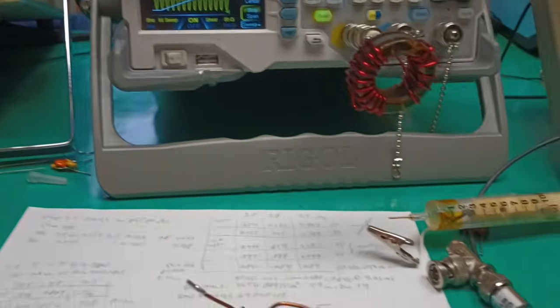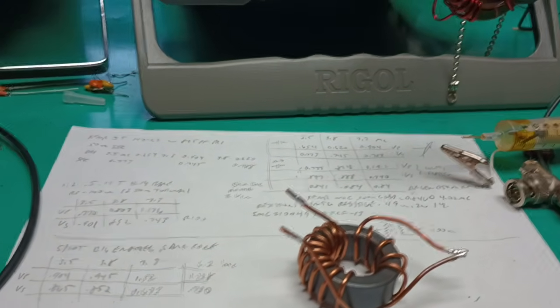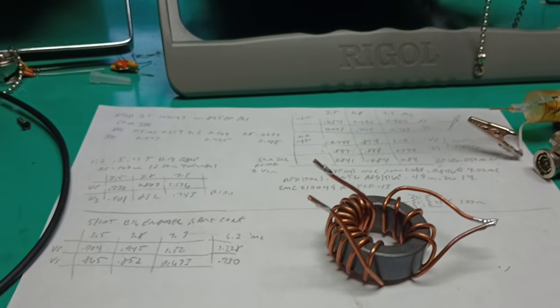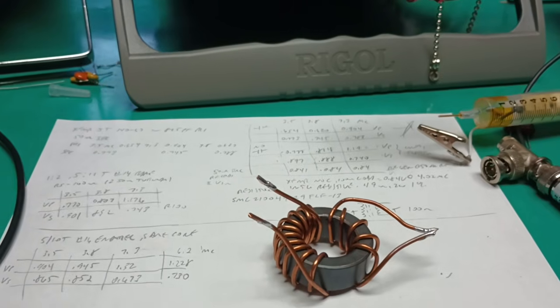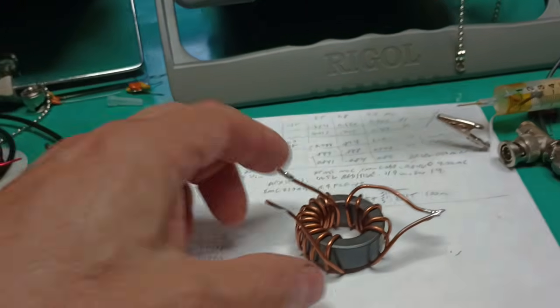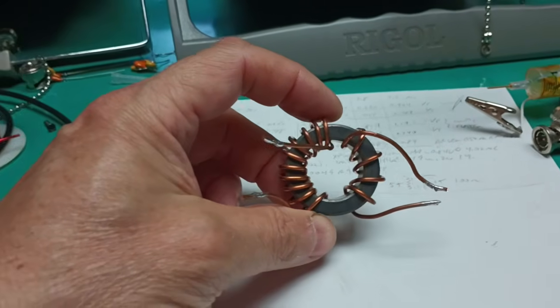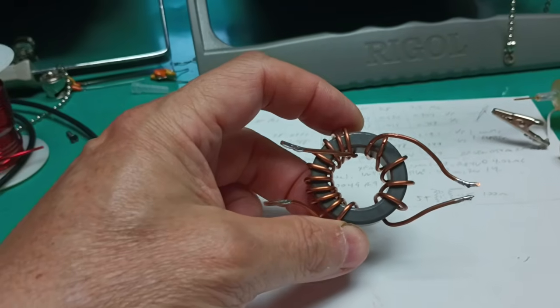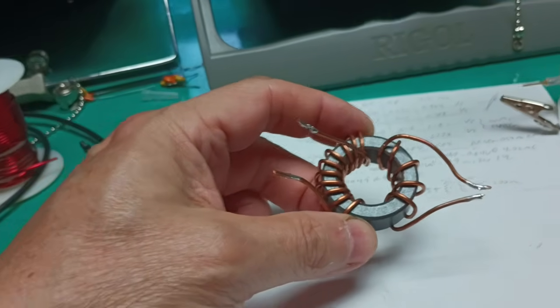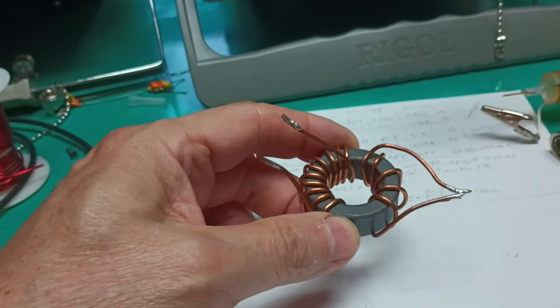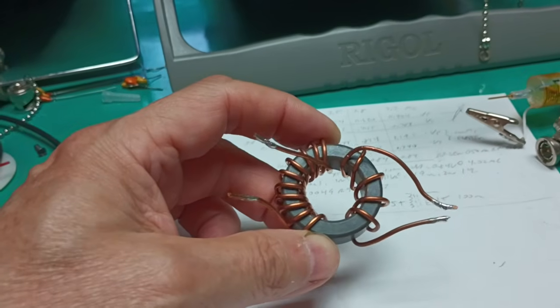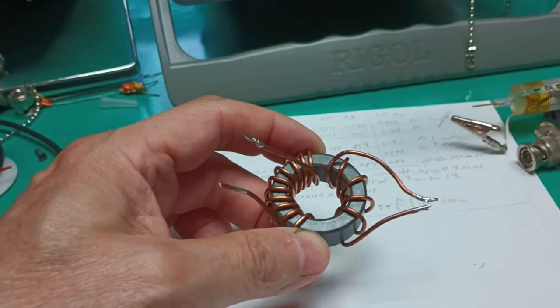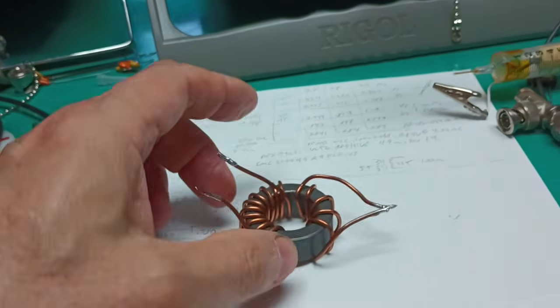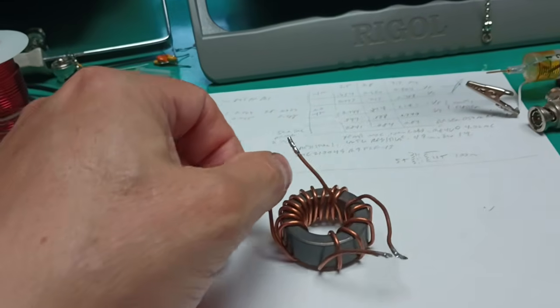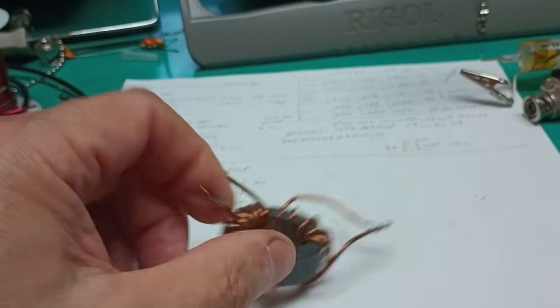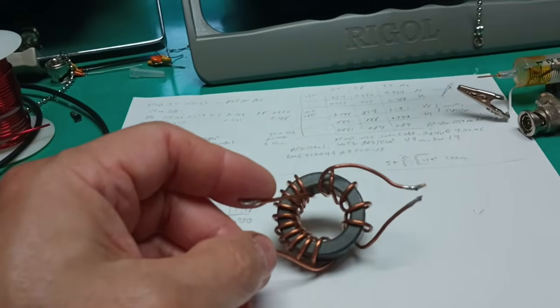Gotcha. Arcing is an RF phenomenon. According to one of the original research papers, electrical arcs tend to have frequency components up in the megahertz range. This transformer is a bit above that. It starts rolling off quite a bit at 1.6 megahertz, so that will tend to reject arcs. And another safety factor is that a sudden, very high energy transient, at some point this core won't pass it because when the core saturates, it opens up. So major safety is included by using this transformer instead of a L network.